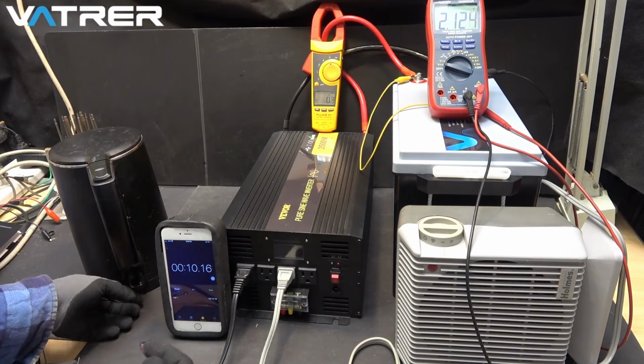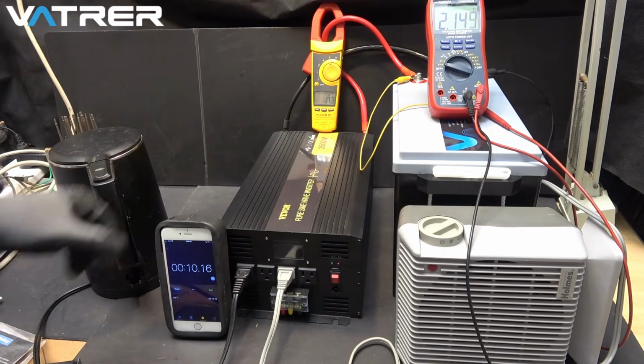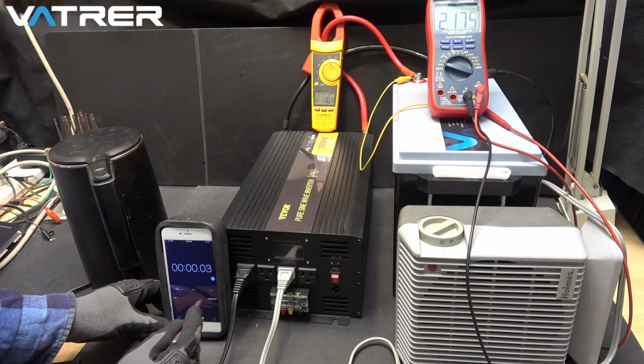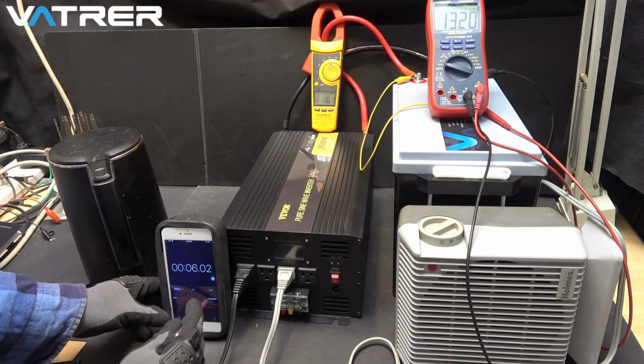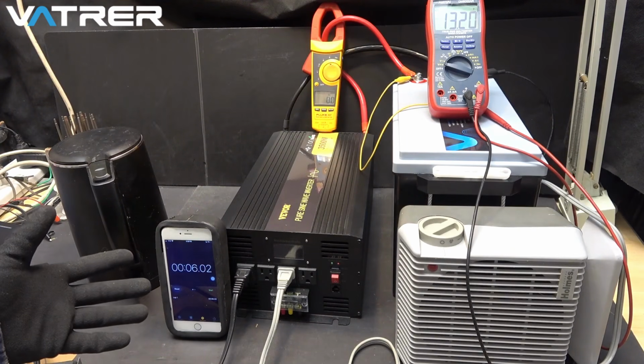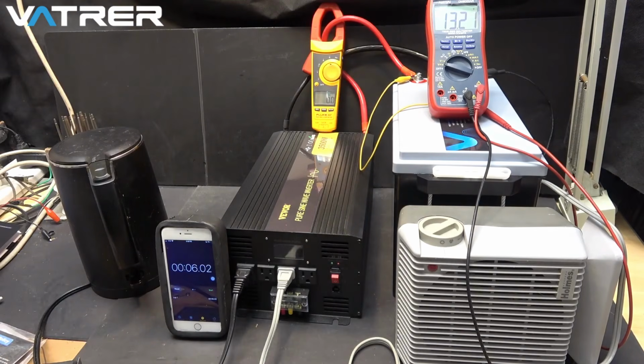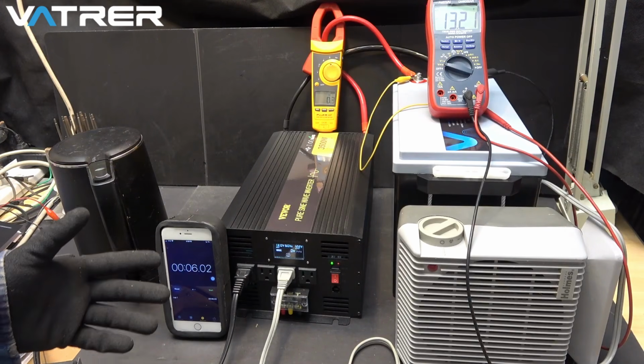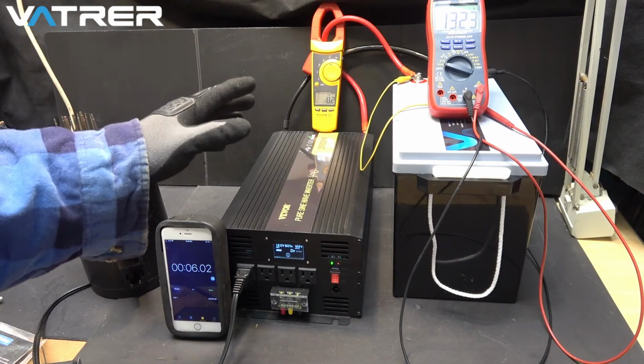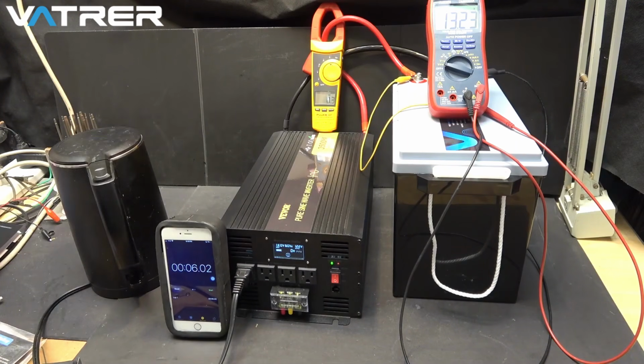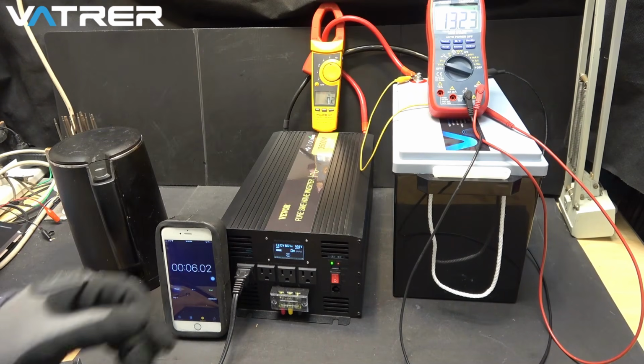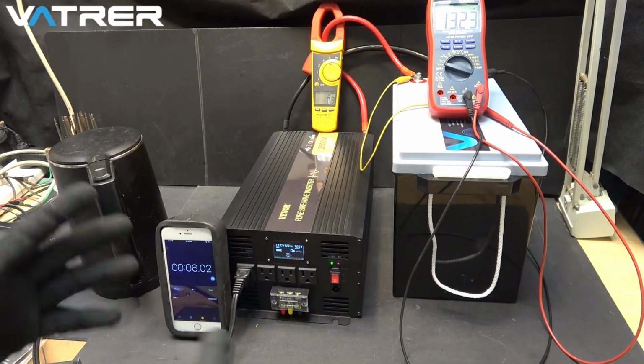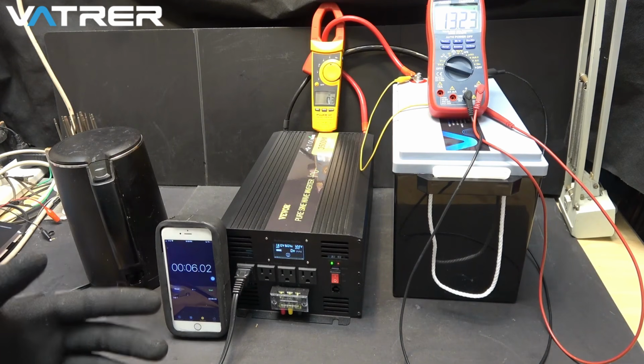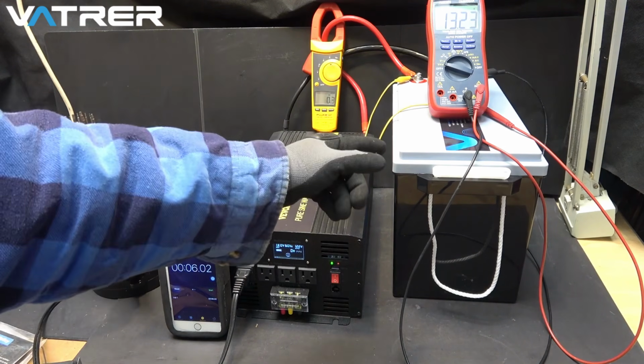So let's turn off everything and start again and see how long it takes... oh, it turns back on. It doesn't take long at all, I'd say about 10 to 15 seconds. 13.2 volts right now, so it's on. Yep, the BMS turns back on after about 10 to 15 seconds. So there you go: if you run over 200 amps, in this case 230 amps, the BMS will shut down to protect the battery from being overloaded after about 8 seconds, and then you gotta wait about 10 to 15 seconds for the BMS to turn back on.